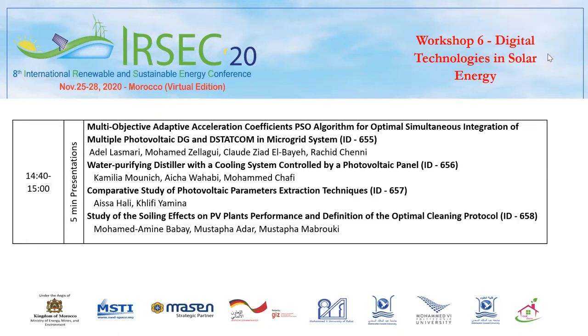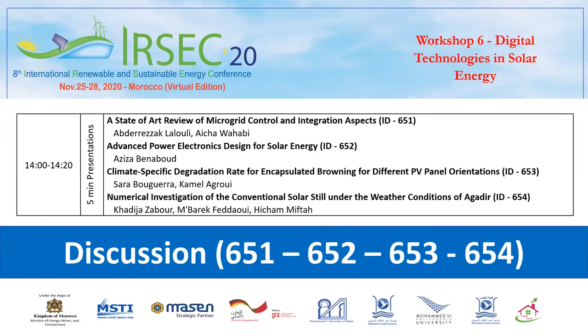Of course, because my domain is the reliability of PV systems, including solar modules and also PV inverters, and different components of the PV system. Recently, there are many methods which use deep learning and machine learning techniques to determine the reliability, especially of PV modules, because there is some uncertainty in the different failure modes. A PV module has different failure modes. Some failure mechanisms are steady and can be determined, such as linear degradation. For example, encapsulant browning is a linear failure mechanism whose failure rate can be known. But there are some catastrophic failures which occur just accidentally, and we cannot predict them.